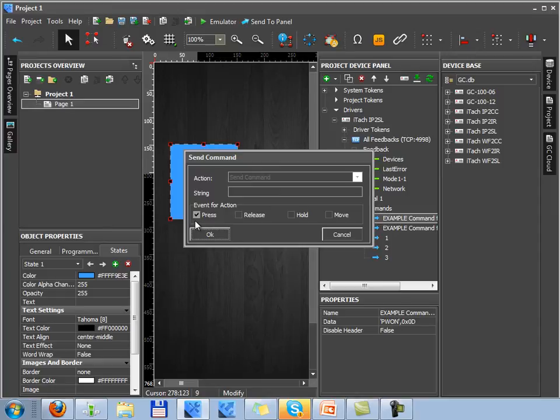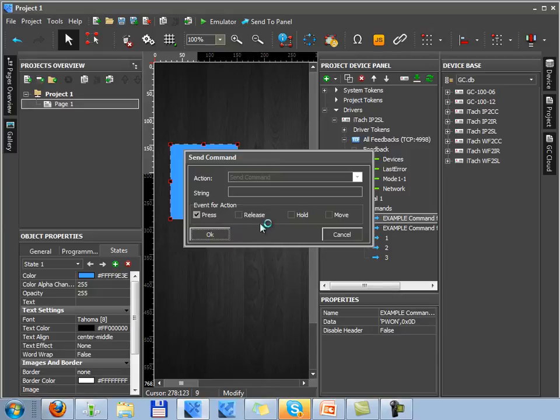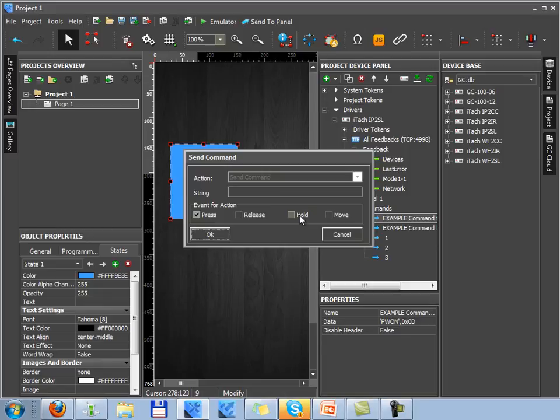When working with devices via RS232 you can select the press, release or hold events. The press event means that the command will be sent by pressing a graphic item. Release means that the command will be sent by releasing the item and hold means that the command will be sent in a cycle by holding this graphic item.